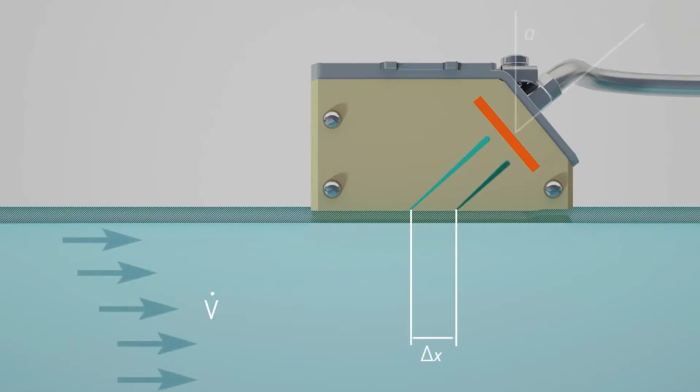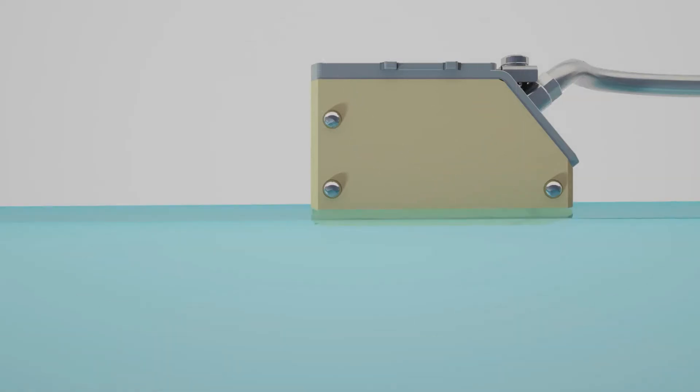Due to the angle alpha of the transducer wedge, this shift causes a decrease of the ultrasonic signal's path length inside the transducer wedge by delta l. This also means a decrease by delta t in the transit time according to the sound speed c-alpha of the transducer wedge. The spatial shift caused by the flow is transformed by the transducer into a time shift. This effect allows for a direct calibration of the transducers.